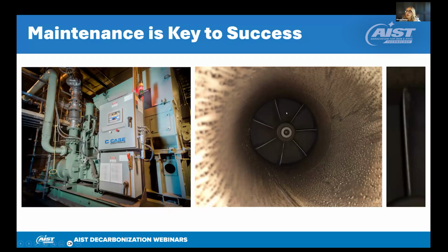And in addition to that, there's a risk to reliability. With the face of the impeller covered in dirt and debris, this piece could vibrate. And after a certain level of vibration, there could be metal to metal contact between these two components as the impeller spins at approximately 70,000 RPM. When you have metal to metal contact, you would have a failure. In turn, that would lead to purchasing expensive rotating components to replace these, and those expensive components also have a long lead time.